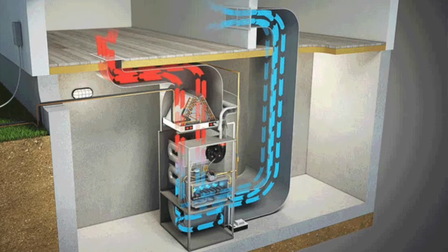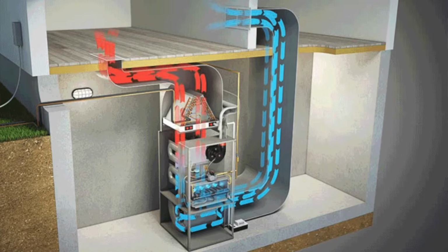Number two, things that lead to furnace failures, I already kind of touched on it, and that is when things are not set correctly, such as the gas pressures. I can't tell you in my years when I was helping other contractors how often I would see them not even own things like a manometer. So of course they're not testing the static pressure on the ductwork because they don't own a manometer, but they're also not setting gas pressures correctly on that furnace. Gas pressures being set too high can cause premature failure, cracking of the heat exchanger, or even worse. And gas pressures set too low can cause other issues such as soot buildup, longer run times, and so on.